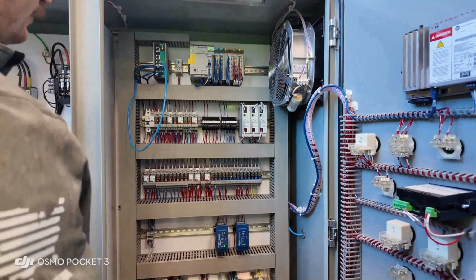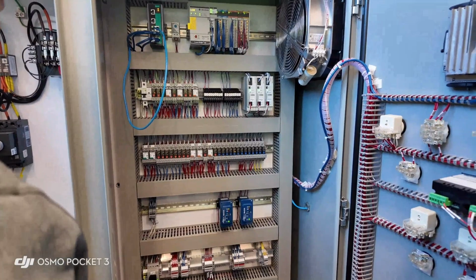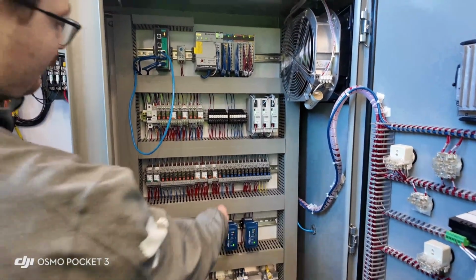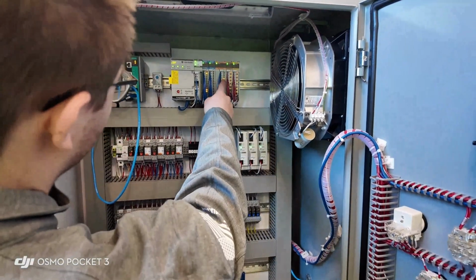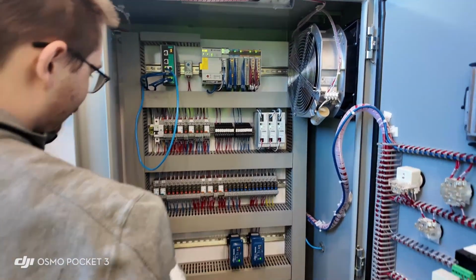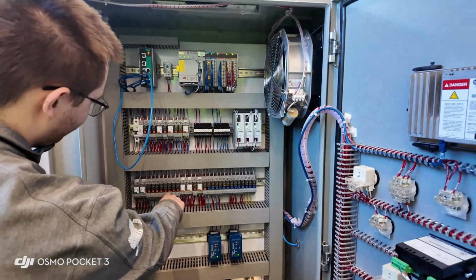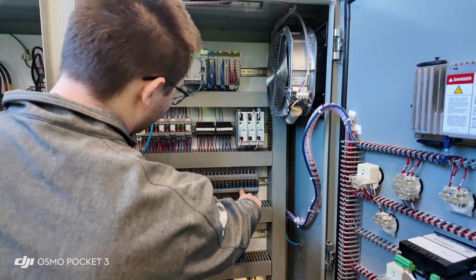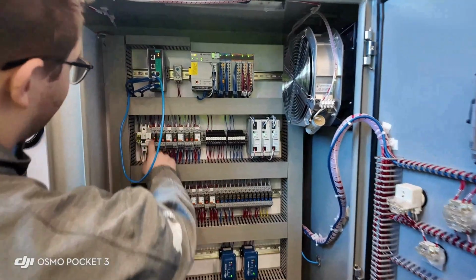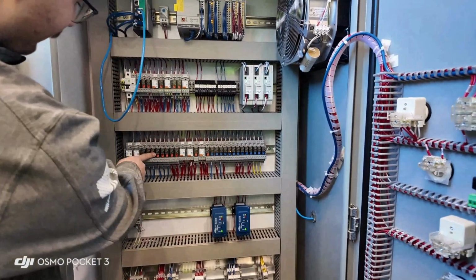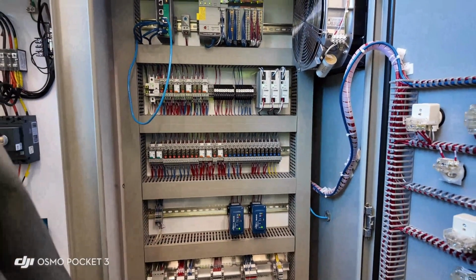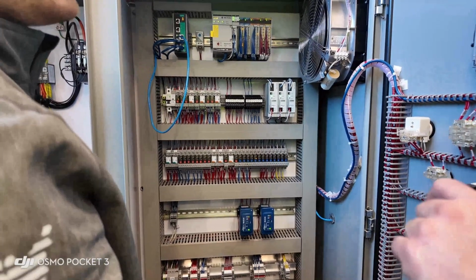This is more or less for relay logic inside the control panel, and your digital outputs all come from this relay up there. The ones that have this orange, that's all 120. The ones with blue are 24 volt relays. Just like your surge device, you can replace the relays, pull them out, and check the part numbers and everything if there's ever an issue with one.